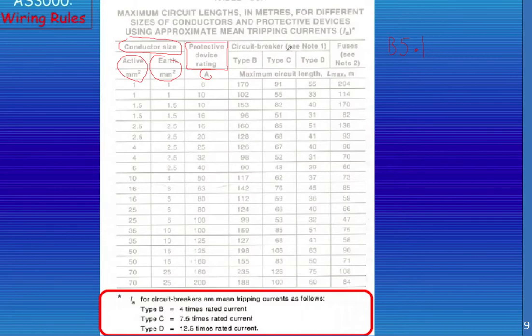And then our circuit breaker, and you see it says see note 1. Now this is note 1 down the bottom here in the red box. It's telling us that there are different types of circuit breaker characteristics. There's characteristic type B, type C, and type D.